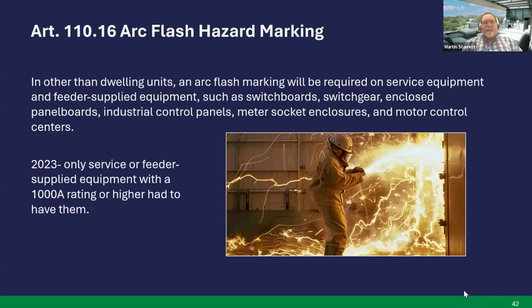Next slide. All right, so this is a big one. If you look at any magazine or manufacturer, any of their top 10, this one's on everybody's list. So Article 110.16, arc flash hazard marking. In 2023, only service or feeder supplied equipment with a 1,000-amp rating or higher had to have this arc flash hazard marking.